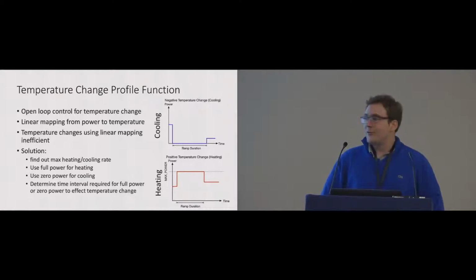One key component which is missing is how to actually change temperatures from one value to another. We chose open loop control for simplicity, and because we have this linear mapping function, we actually know which power to set for a given temperature. However, it's very slow to just switch voltages corresponding to the output temperature, for example going from 20 to 30 degrees Celsius. Actually, what we want is to change the temperature at the maximum rate.